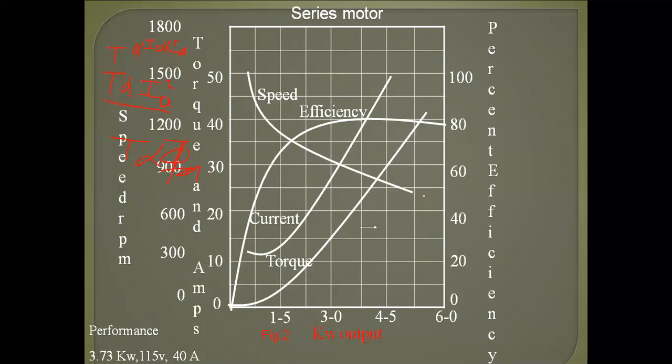The speed-torque characteristic of a DC series motor is also known as the mechanical characteristic. Speed falls sharply with an increase in torque for smaller values of load. But at higher loads, the speed drops linearly but slowly with increase in torque. Hence, series motors are best suitable for services where the motor is directly coupled to the load, such as fans, whose speed falls with increasing load torque.